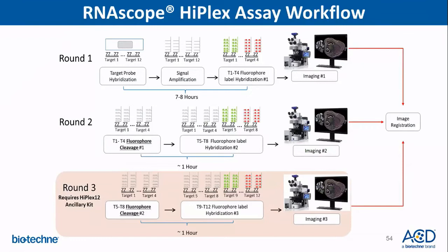In round 2, you will do detection for T5 through T8 after cleaving the T1 through T4 fluorophores, and then you would go on to imaging for round 2. And then finally, if you're doing a 12-plex assay, which would require the HiPlex ancillary kit, you would cleave the T5 through T8 using a chemical cleavage, followed by T9 through T12 fluorophore detection and image for round 3. And finally, you will use our image registration software to basically stitch the images from round 1, 2, and 3 together to create a merged image.